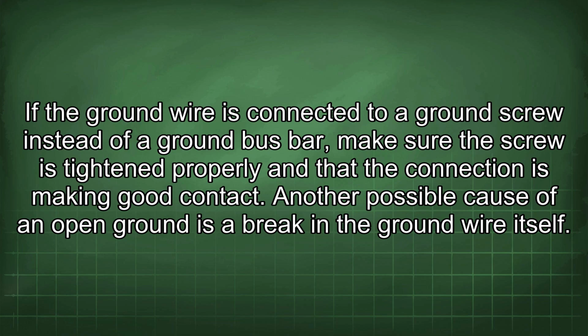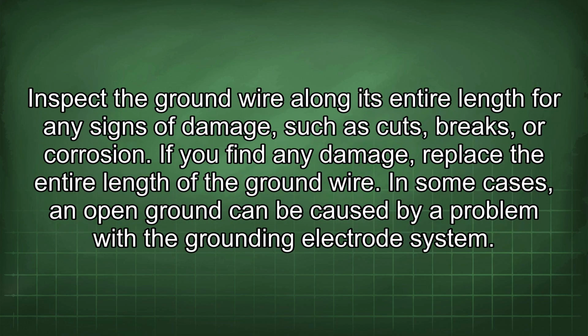Another possible cause of an open ground is a break in the ground wire itself. Inspect the ground wire along its entire length for any signs of damage, such as cuts, breaks, or corrosion. If you find any damage, replace the entire length of the ground wire.